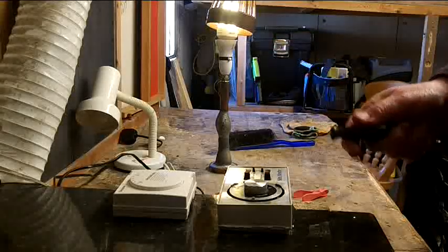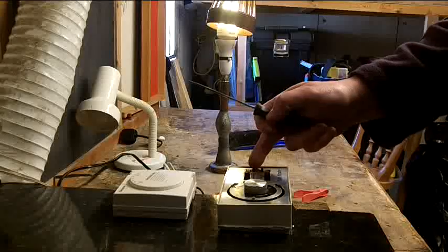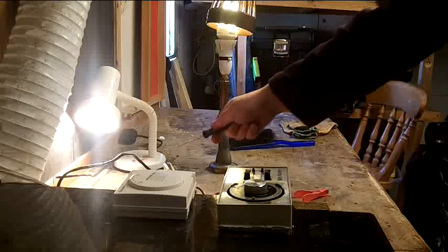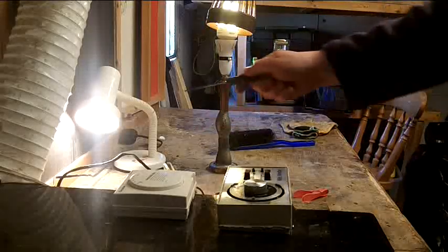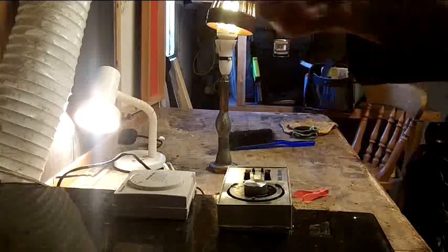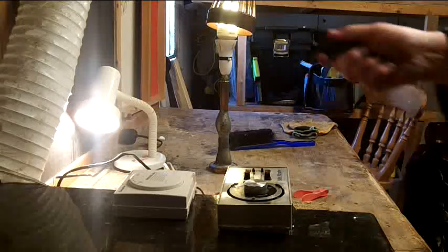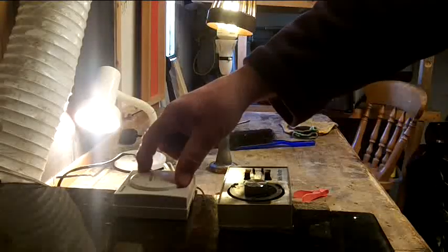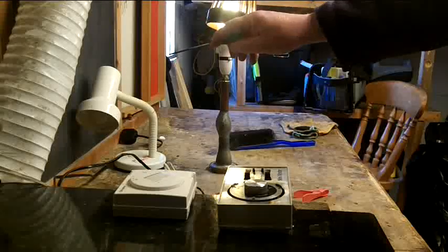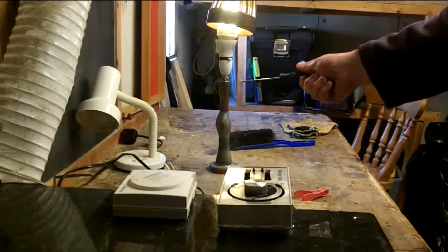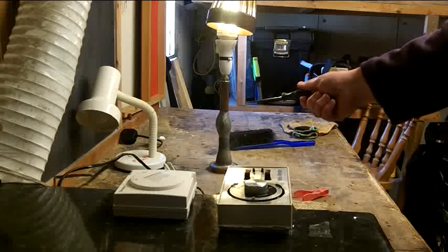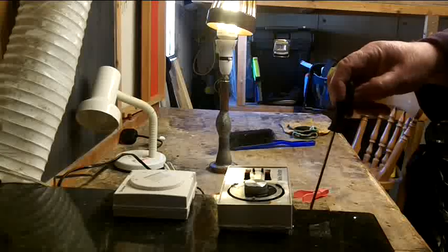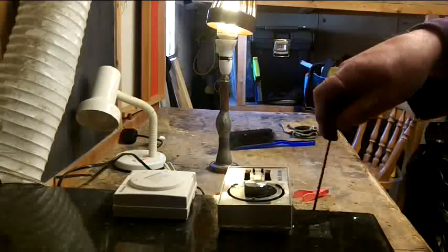The other channel, which is going to central heating, works rather differently. By putting that on you've got central heating now because the pump's kicked in, represented by this lamp, and now the pump is taking the hot water all the way around the radiators, and that'll only stop when the thermostat has got warm enough and it comes down, and it'll turn the pump off. But the boiler's still running, and the boiler will run until the boiler thermostat knocks that off, and it'll continue cycling. That's why it's very uneconomical, and that's why things have got better since.